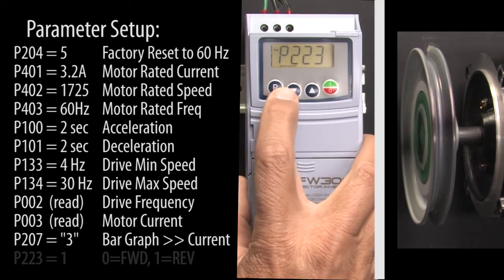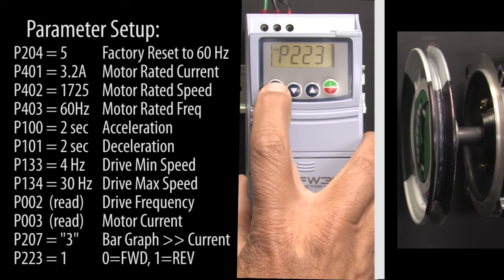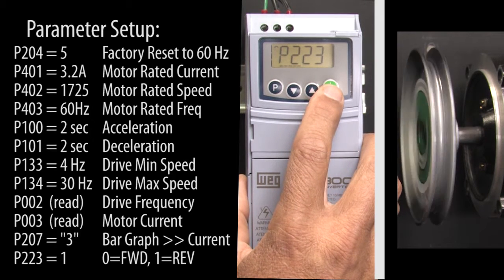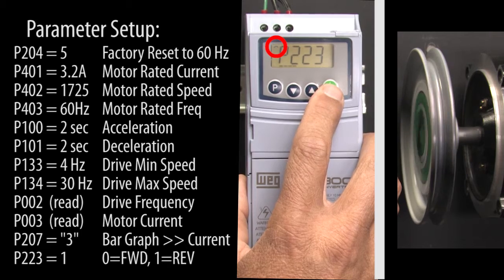Parameter 223 controls forward and reverse. Stop the motor, change it to a 1, hit P to accept that, and now when we run the motor it rotates in the opposite direction and the rotation indicator up here also changes direction.